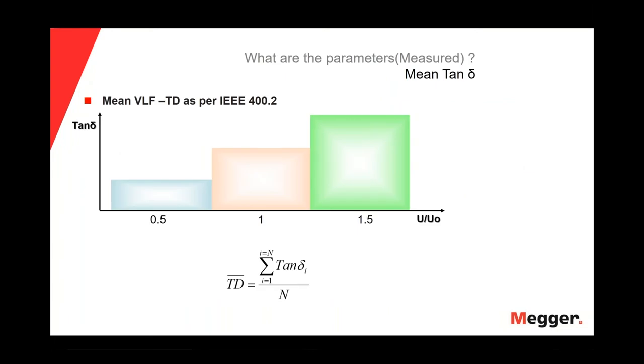So, what parameters will we measure? The first one is the mean VLF tan delta, or the mean value of the tan delta. As we can see in the equation, the mean value of the tan delta is the summation of all the individual tan delta values divided by the number of values, in this case 30. So we sum all the tan delta values from each voltage step and divide by the total number of measurements, in this case, once again, 30.